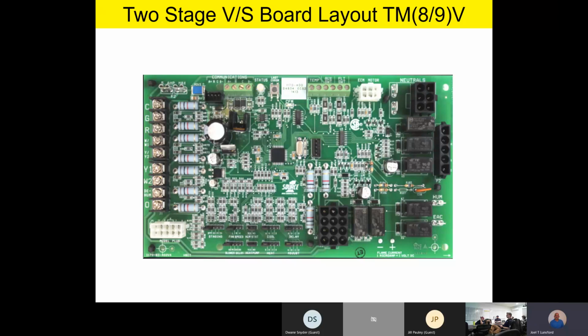So starting out over on the left-hand side, like we normally do on the low voltage terminal strip, C is going to be our 24 volt common. This is where we're going to hook up our thermostat and our low voltage wirings. G will be our fan call. This is pretty conventional, isn't it? And so again, just very, very straightforward. R is 24 volt hot. W/W1 is going to be our first stage heating call.